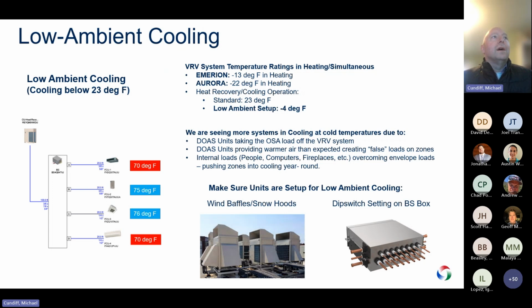So if you go to the top right up there, and our Emerion units is our newer line, you get negative 13 degrees in heating. So that's what they're rated down to. Aurora, you get negative 22 in heating. And then the heat recovery cooling operation standard, and this is pretty typical of most manufacturers, is going to be right around 23 degrees. So without anything, you can do cooling down to 23. You can do simultaneous operation down to 23. If it's going to be below 23 and you want units in cooling, or you expect them to be in simultaneous mode, we need to do some things to set those up for low ambient cooling. With our setup, we can get down to -4.